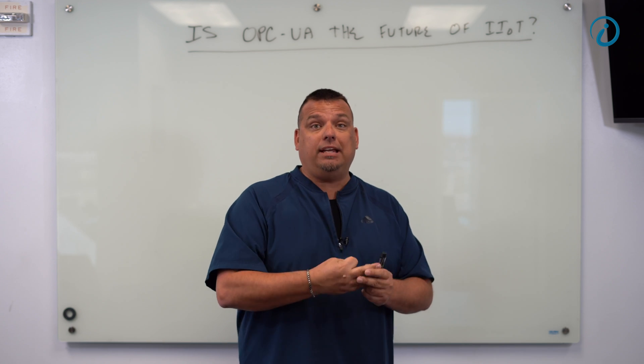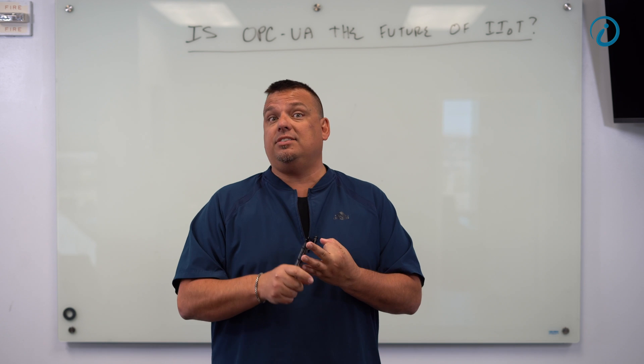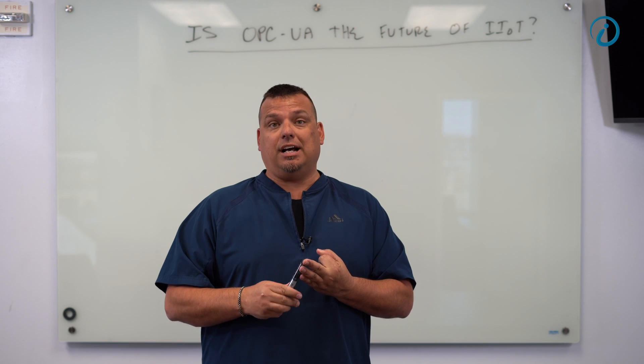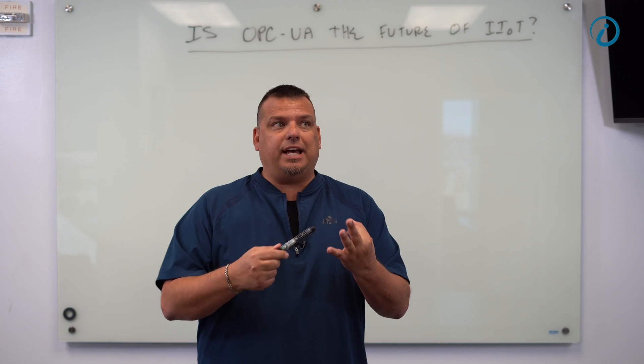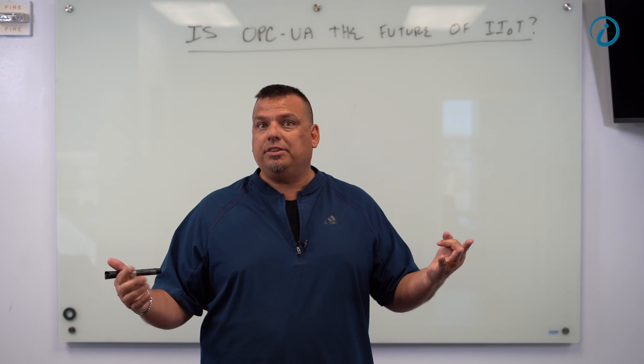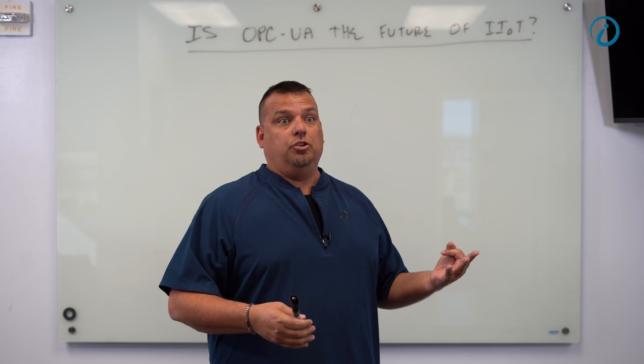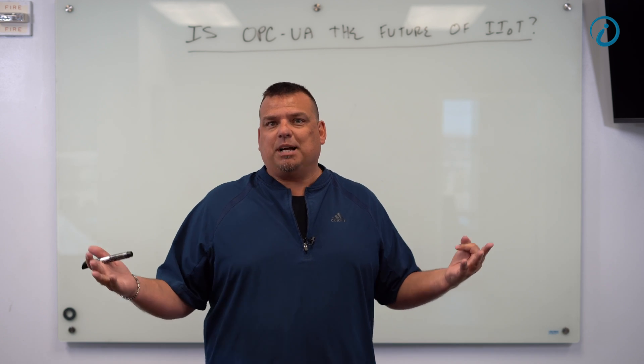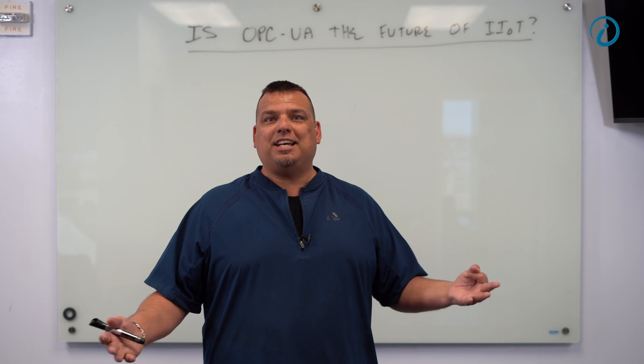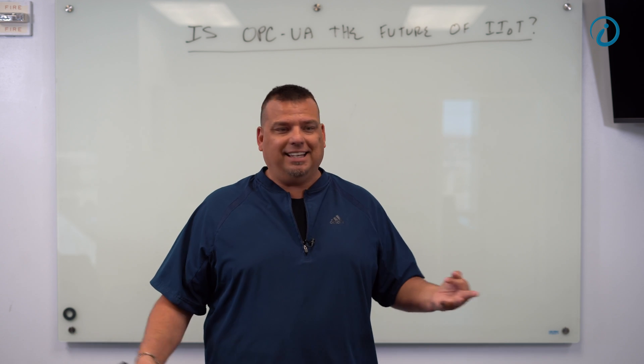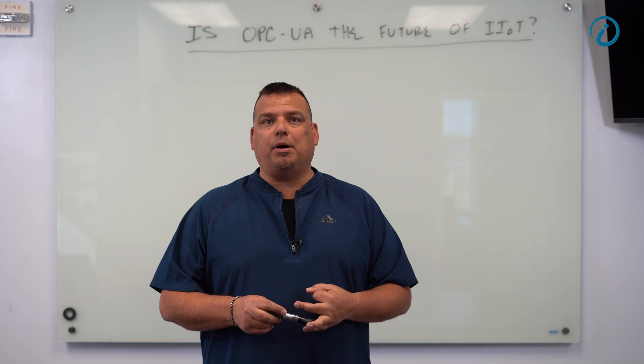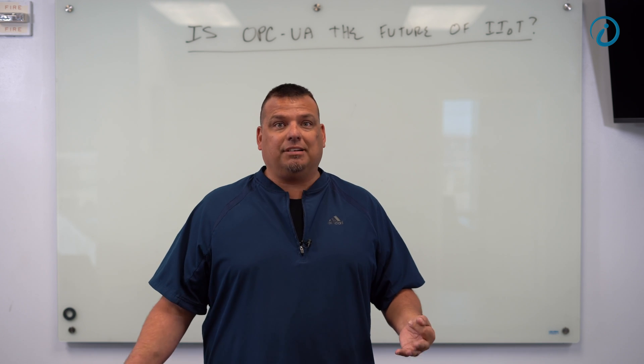Number three, it is lightweight and stateful. In our opinion, those are the three things that all IIoT protocols have in common. You've got to be lightweight and stateful. It can't take up a ton of bandwidth in your network. Why? Because everything in your business is going to become smart and be on the network. If everything takes up a ton of bandwidth, you don't have any bandwidth left. Report by exception, there's no point in publishing data that hasn't changed.